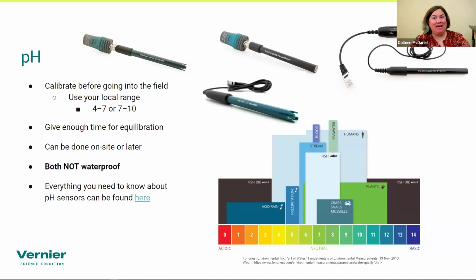The biggest key thing is both the Go Direct and the LabQuest sensors are not waterproof. So basically you do not want to submerge them much more than 2/3 of the sensor body right here. The Go Direct sensors have this BNC connector here that is not waterproof. Same thing with the LabQuest pH sensor. Along with the body here, there are some electronics in it that are going to cause some issues if they get wet. One of our jokes around here is we say everything is waterproof at least once. And then after that, not so much. So that's something to keep in mind.